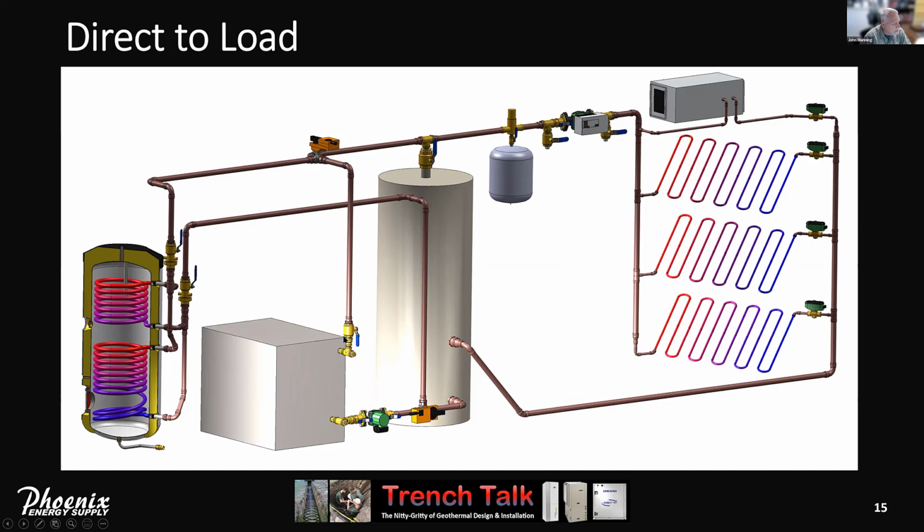This diagram also illustrates the ability to have a couple of three-way valves that would shift when you get a call for domestic hot water. This happens to be an indirect tank with two internal heat exchangers. We pipe them in parallel to really reduce pressure drop and maintain the type of flow the heat pump wants to see. So it's important to look at the piping. The surface area of heat exchanger in this tank is critically important. Stiebel Eltron makes a very good tank. The new net zero stainless steel tanks even have more surface area.